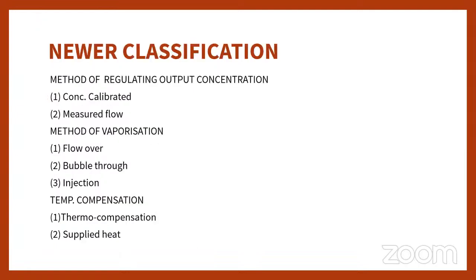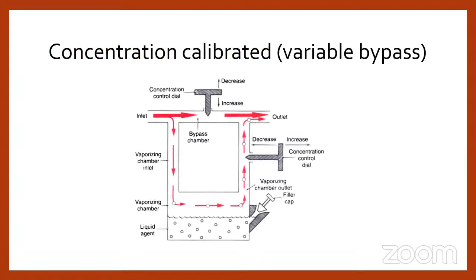Well, coming to the newer classification, a few classes from the previous classification have been omitted, and this is for our convenience. The method of regulating output concentration: number 1, concentration calibrated, and the second one is measured flow. Another type of classification is method of vaporization. This we have already discussed in the previous slide: flow over, bubble through, and injection. Temperature compensation: when coming to the temperature compensation, there is thermo compensation and supplied heat. These three are the major classifications that we are following as of now. I'm going to discuss a few of them in detail.